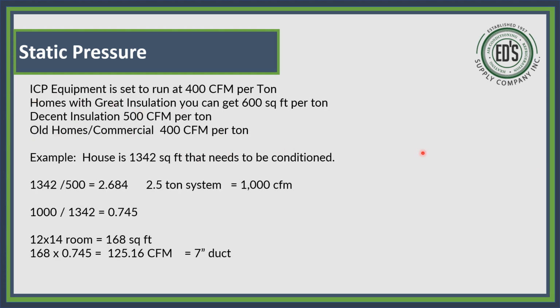Now, let's look at this. Here is the old rule of thumb that we used back in 1994, and it's still pretty close to the same. ICP equipment is set to run at 400 CFM per ton. They would love it at 350, but let's just say 400 CFM is a rule of thumb. Homes with great insulation, that could be spray foam, tight insulation, vapor barriers with insulation, you could get away with 600 CFM, 600 square feet per ton. Decent insulation houses, which is the 80% majority, 500 CFM a ton. But old homes and commercial properties should be 400 CFM a ton.